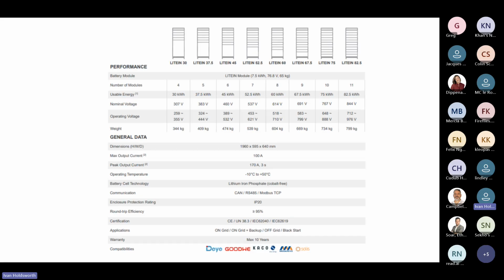You can have between 4 modules and 11 modules in a tower. And here you can see, because it's in series, the voltage of each stack will go up. For example, a tower of 4 will be about 300 volts, and a tower of 11 will be 850 volts.